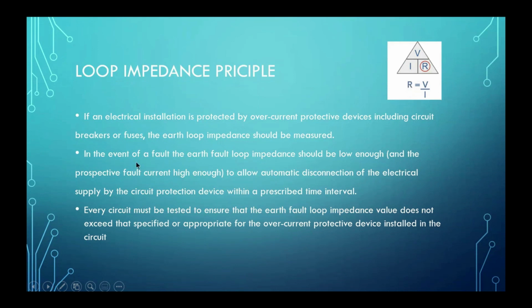Okay. In the event of a fault, the loop impedance should be low enough, and the prospective fault current high enough to allow the automatic disconnection of the electric supply by the circuit protection device within a prescribed time interval. So in this condition, this impedance is related to the protection device. This condition must be met. If you have a protective device in your circuit, the impedance must be low enough. Okay, understand? So the impedance must be low enough and follow the safety standard. There's a standard to follow. Later I will show you. Okay, understand?